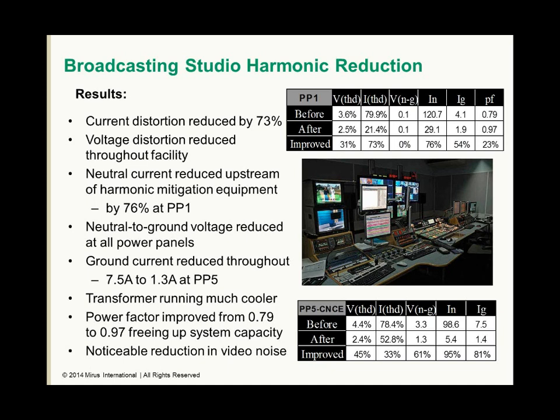The drop in ground currents was dramatic due to the reduction in third harmonic distortion. What was happening was the third harmonic distortion was pushing current through the input filters on all of the power electronic equipment through to the ground and creating the ground currents. And that was also causing the video noise. So the video noise was noticeably reduced with the application of the HMT devices. The transformer ran much cooler, and with improved power factor, system capacity was freed up.